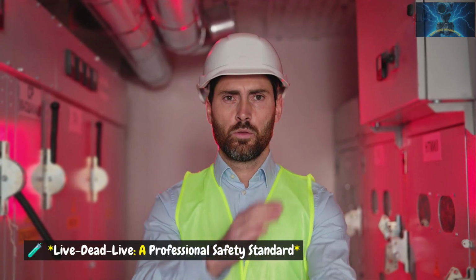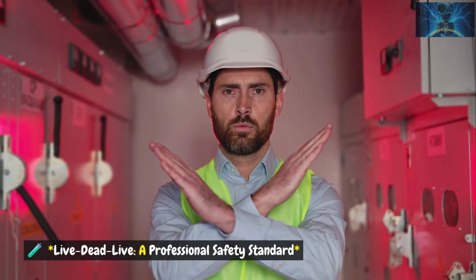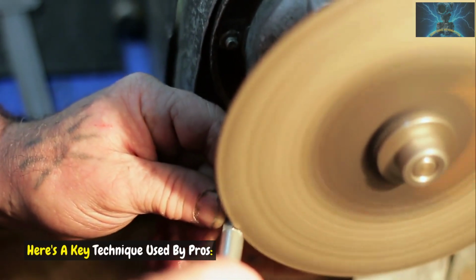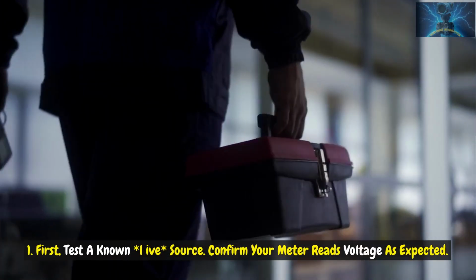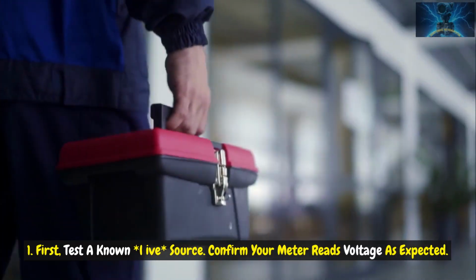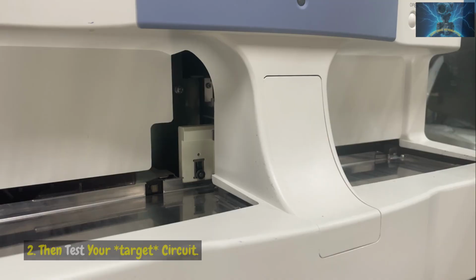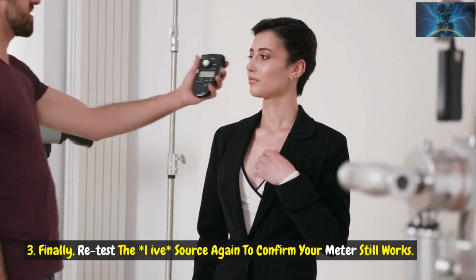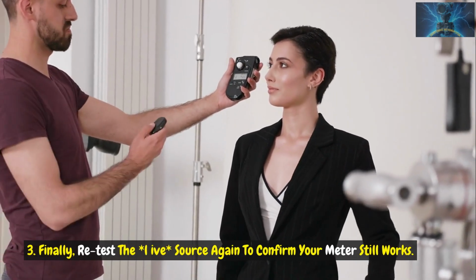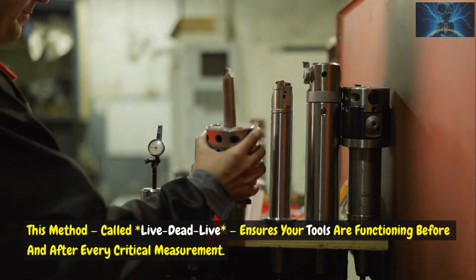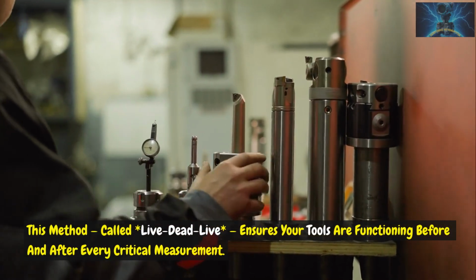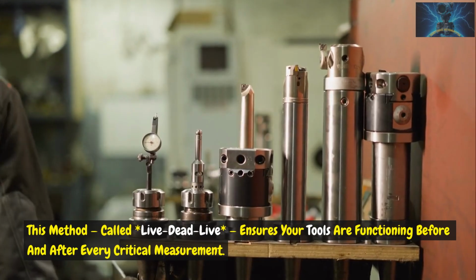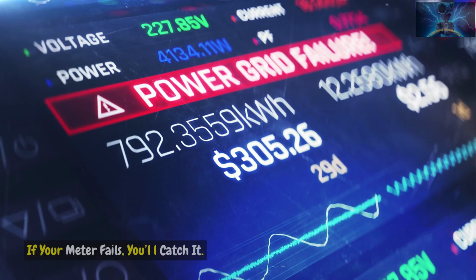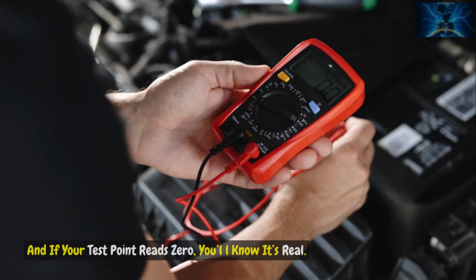Live, dead, live, a professional safety standard. Here's a key technique used by pros. 1. First, test a known live source. Confirm your meter reads voltage as expected. 2. Then test your target circuit. 3. Finally, retest the live source again to confirm your meter still works. This method, called live-dead-live, ensures your tools are functioning before and after every critical measurement. If your meter fails, you'll catch it. And if your test point reads 0, you'll know it's real.